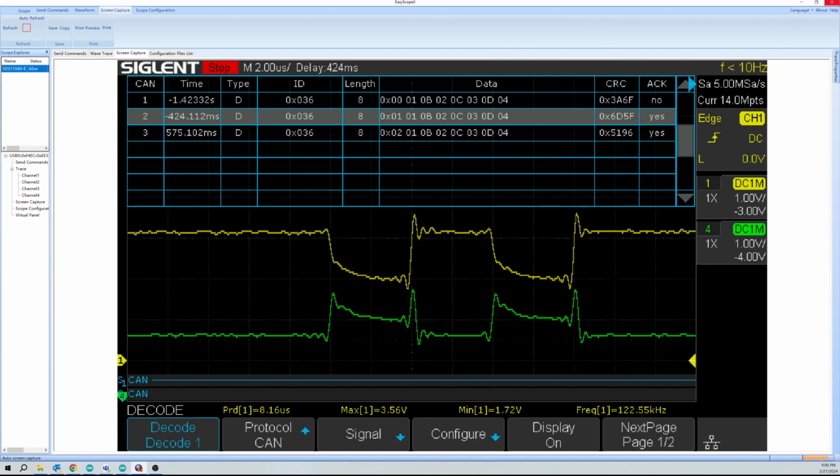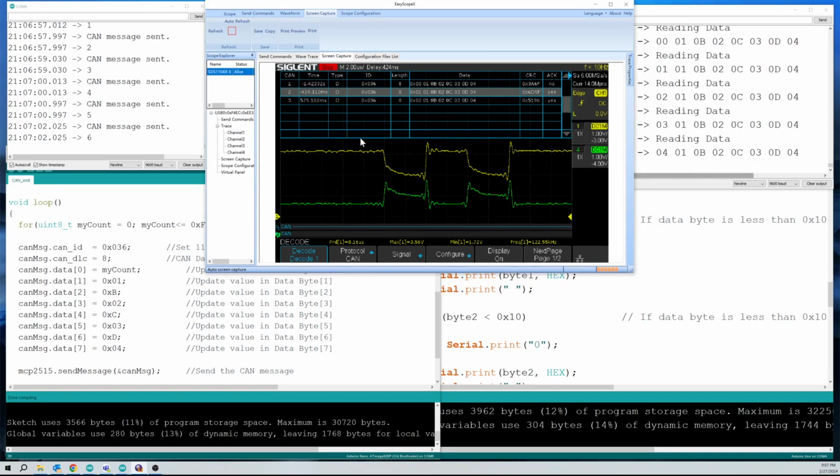So I guess this, we'll call it the healthy network, where everything here we can see 1, 2, 3, 4, 5, 6, 7, 8, 9, Alpha, Bravo. Every message is being received. And so F, and then it starts over at 0 again. So 0 through F on our first byte. We're transmitting our message every second, and this is the healthy network. Next, we're going to attack this network and see what happens.